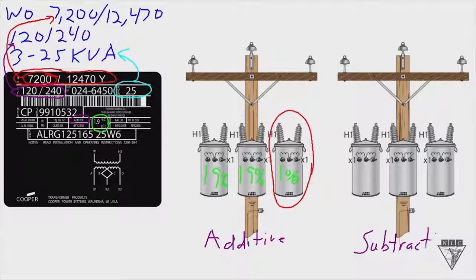Okay, so that's the criteria for choosing the right transformers, single-phase transformers, when banking or paralleling transformers. You need to know the circuit voltage, the service voltage, the size transformers you need, and then try and get the polarity to match, and try and get the impedance as close as possible for all three.